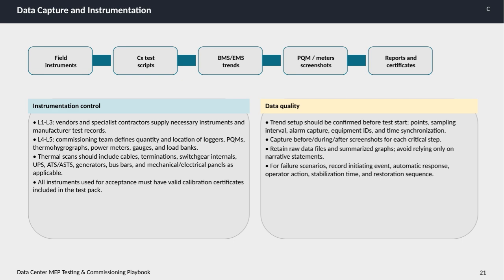During testing, capture screenshots before, during, and after each critical step to provide a clear record. Additionally, it's important to retain raw data files along with summarized graphs, rather than relying solely on narrative explanations. In failure scenarios, detailed records should be maintained, including the initiating event, the automatic system response, any operator actions taken, how long it took to stabilize the system, and the sequence used to restore normal operation. All of these measures together ensure the integrity and thoroughness of the testing process, helping us to validate system performance and reliability comprehensively.